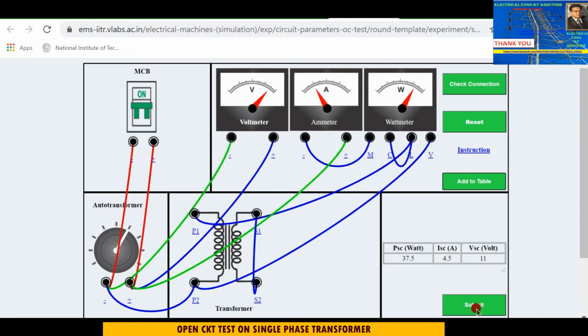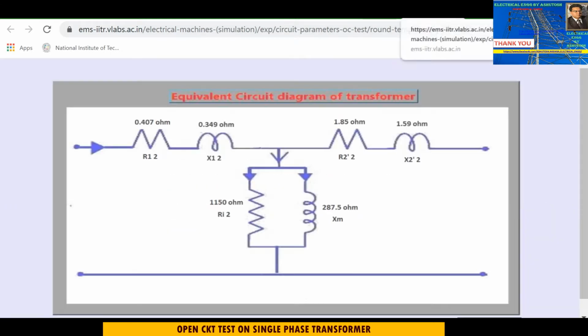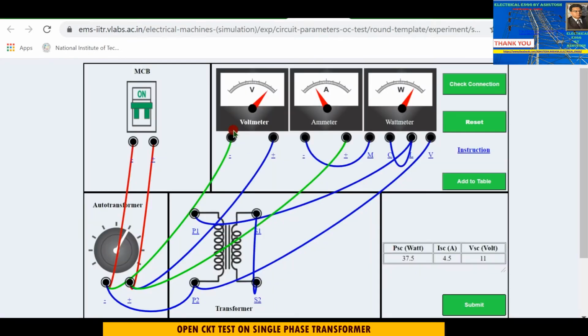And finally, when you submit, the equivalent diagram is automatically drawn like this. As you can see, this is the equivalent diagram of the transformer. So guys, first of all we have to reset this connection, so that we can connect the circuit and perform the open circuit test and short circuit test.